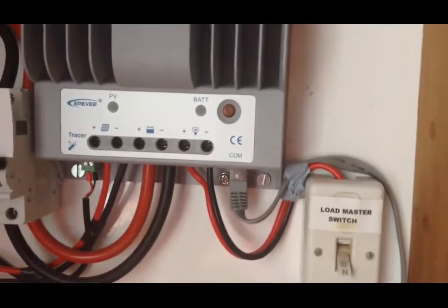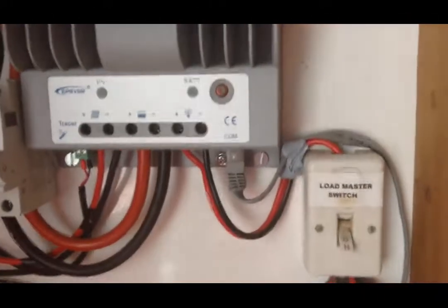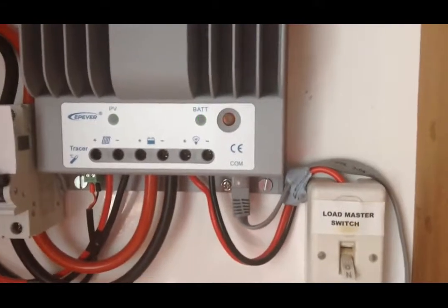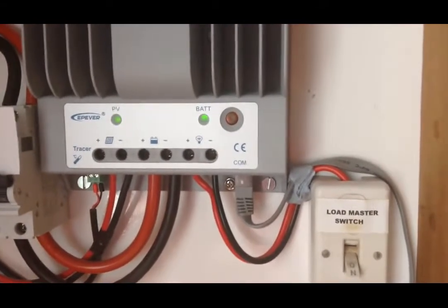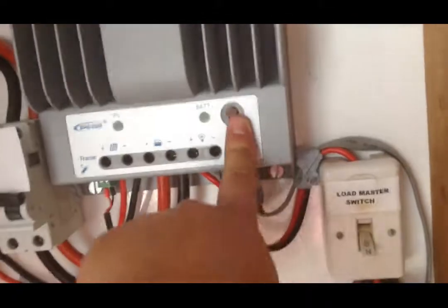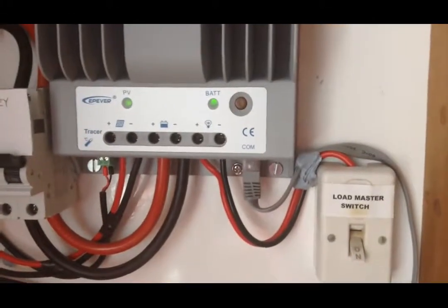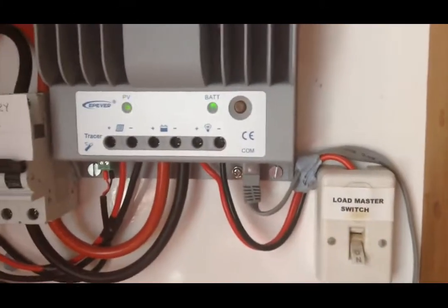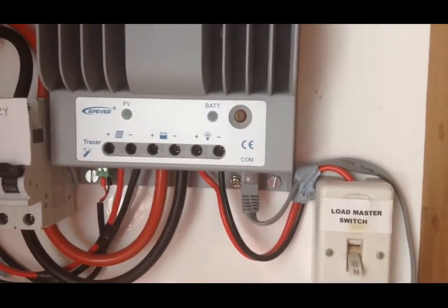Also, the charge controller does have built-in protections. Most of them do. So if there's a short in the circuitry somewhere, it will isolate the output, and most of them will try reconnecting 2 or 3 times, and if the fault is still present, it will latch out, and the only way to make it turn on again is to reset the charge controller. But it's better not to rely on those protections. It's better to use fuses and circuit breakers. So that's this part of the system.